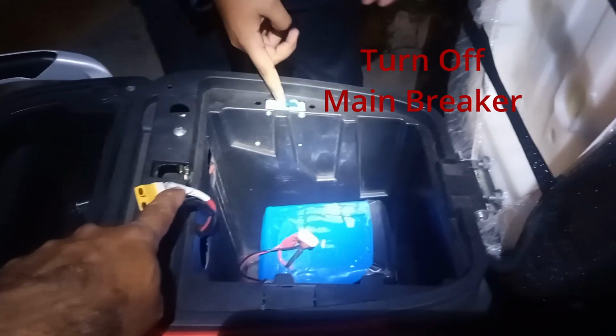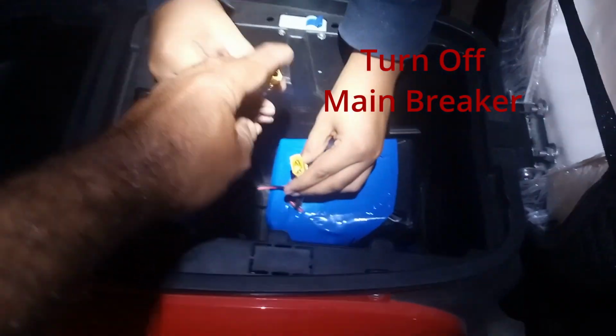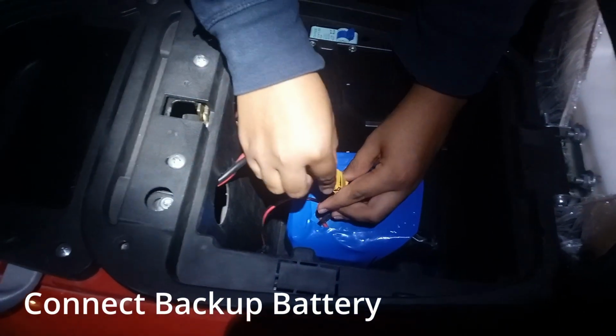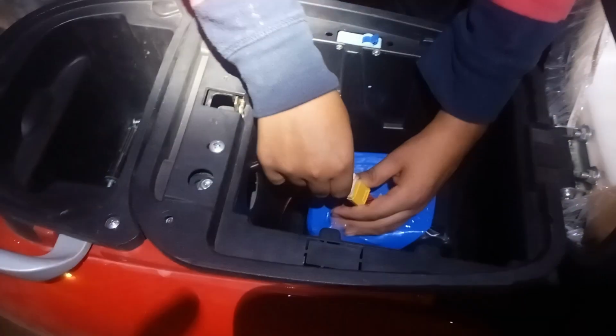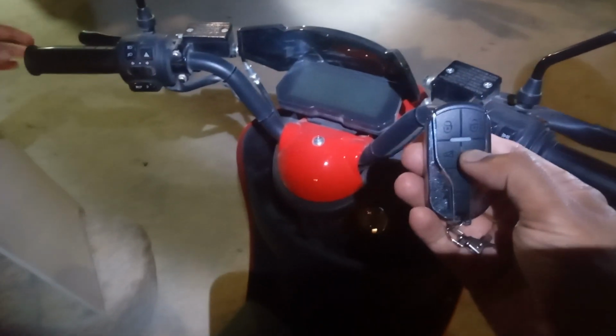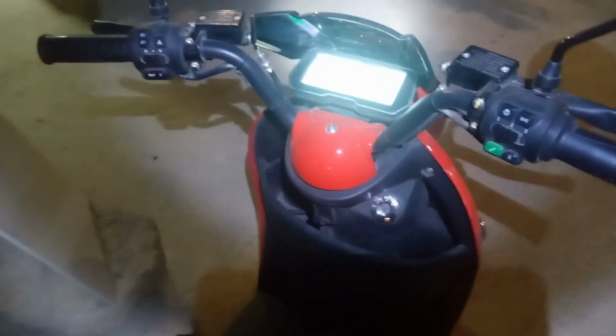Advantages. Batteries can have different capacities and cutoff levels as long as they share the same voltage. Extends the lifespan of both batteries by using them separately. Eliminates unnecessary load when the backup isn't in use. Potential issues. Requires manual intervention to switch between batteries. May need additional wiring and space for the switch installation.